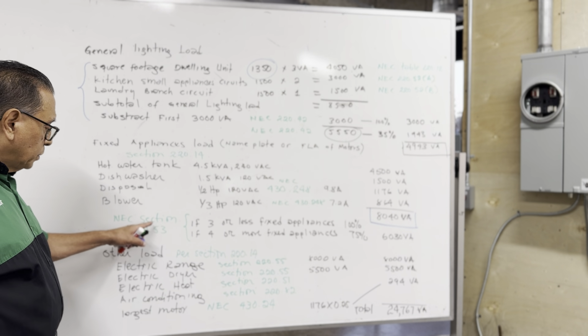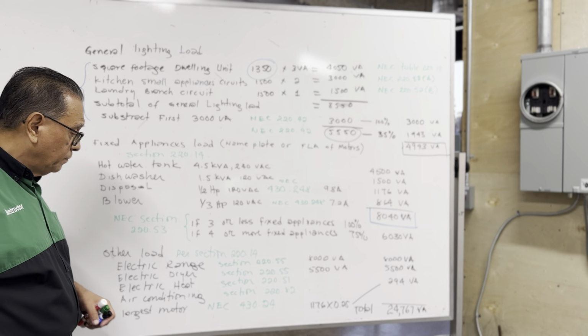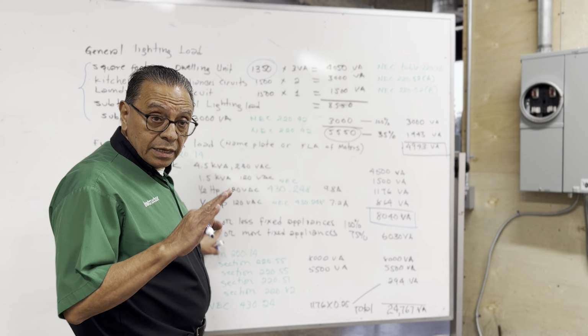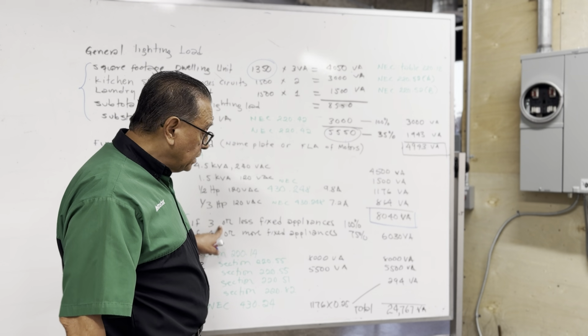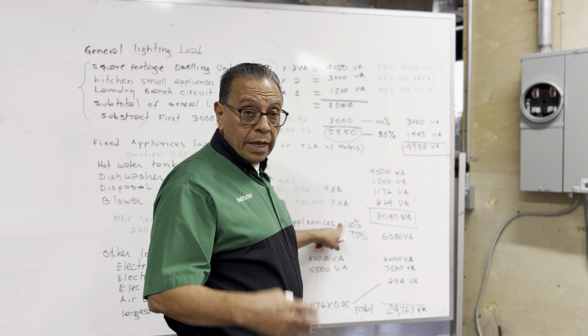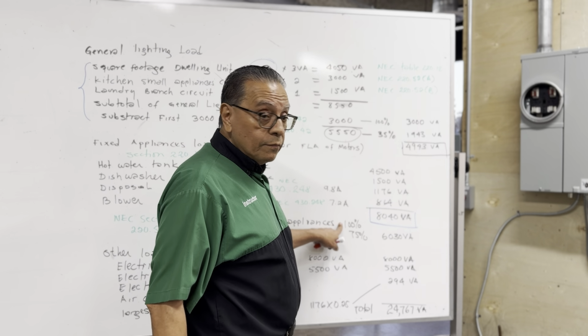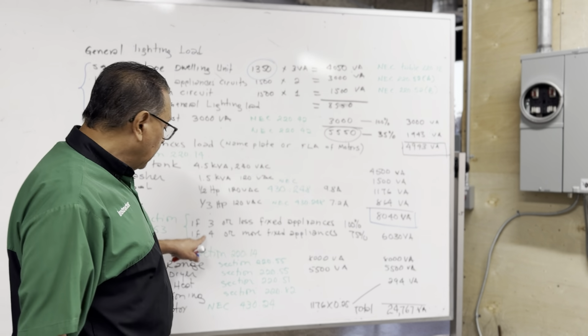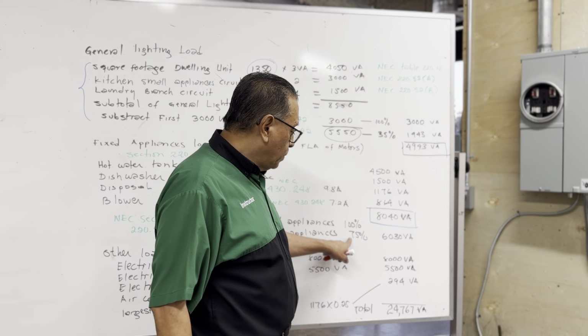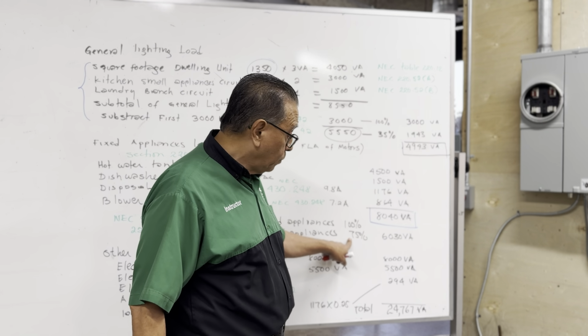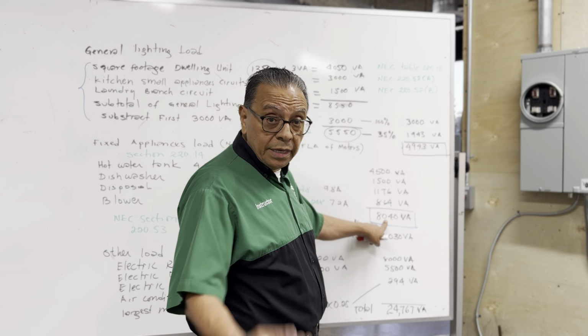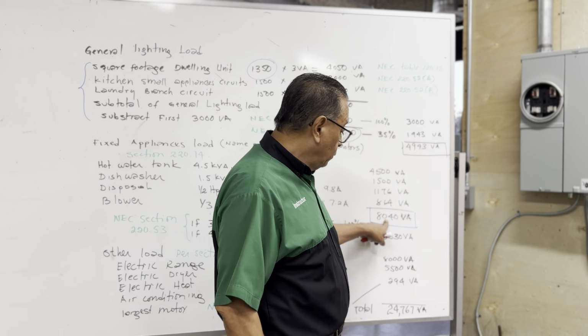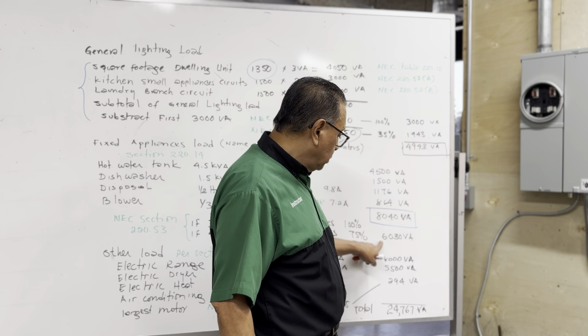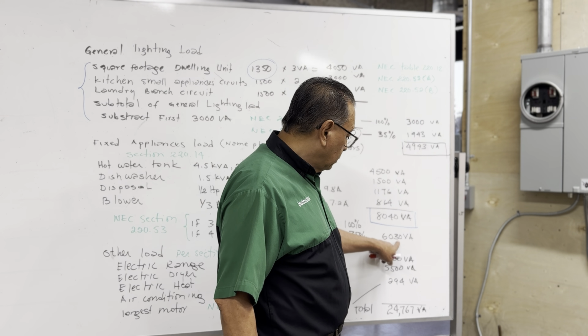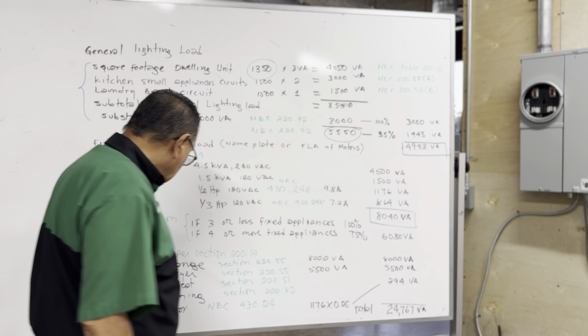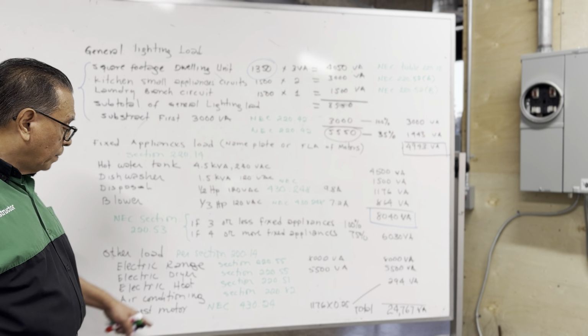According to Article 220.53, if I have 3 appliances in this section or less, I request from the service company the 100%. If I have 4 or more, the 75%. I have 4 in my example, so I will be asking the service company to provide me for this dwelling unit with the 75% of this, which is 6,030 volt ampere.